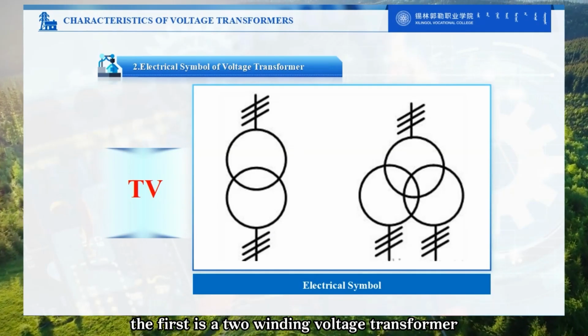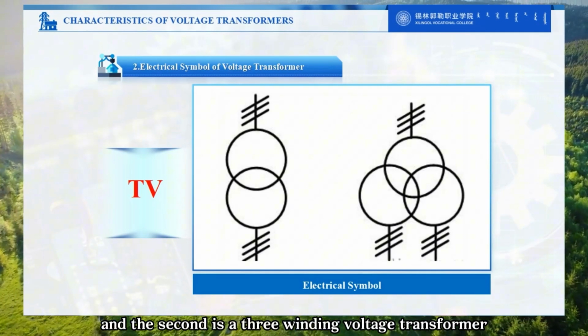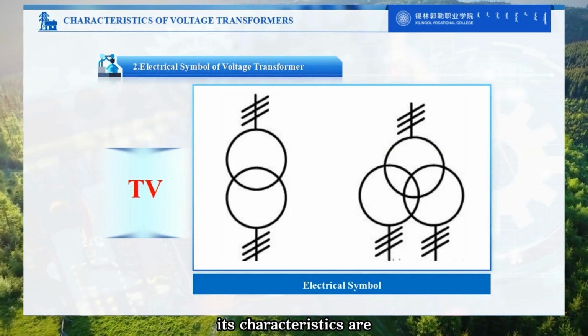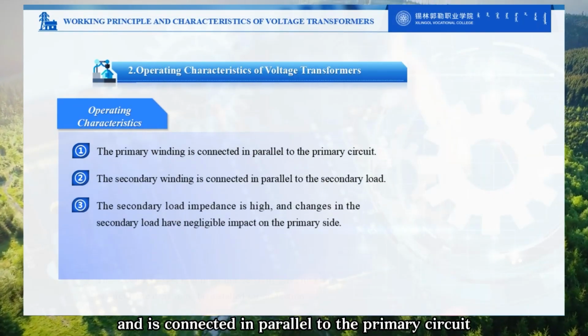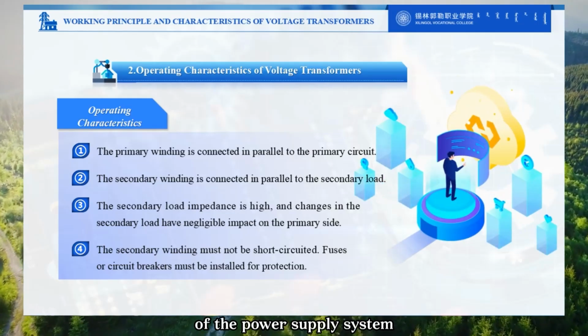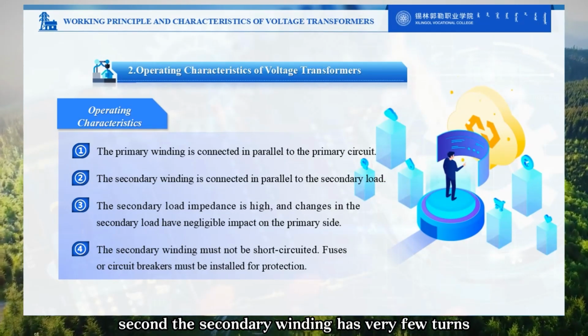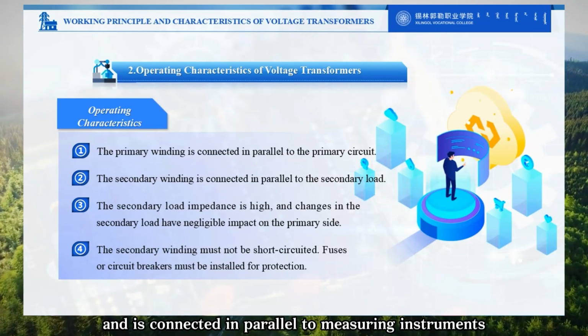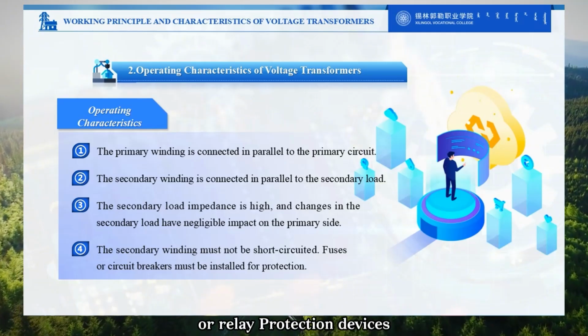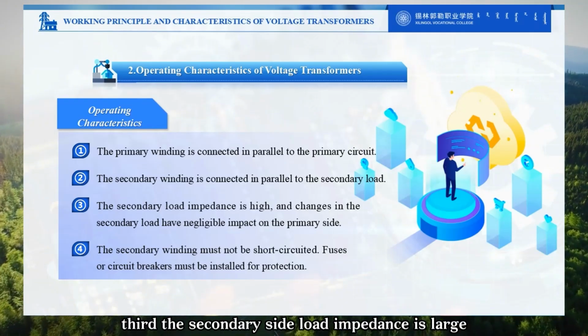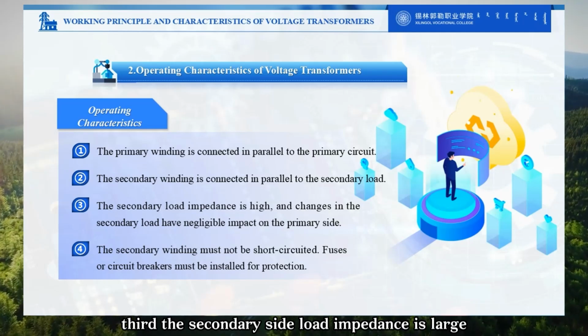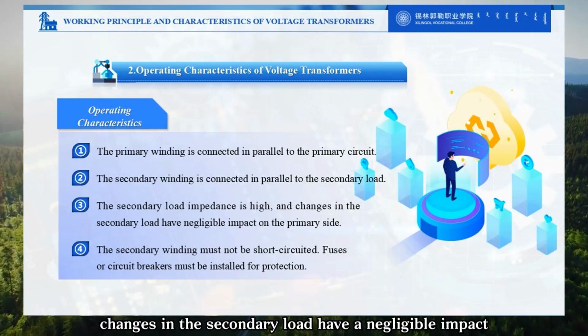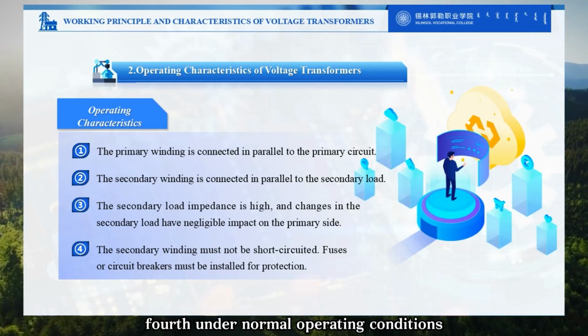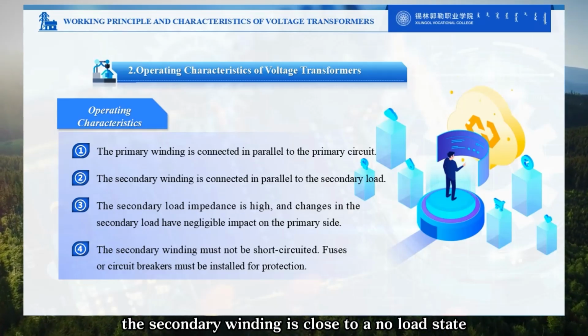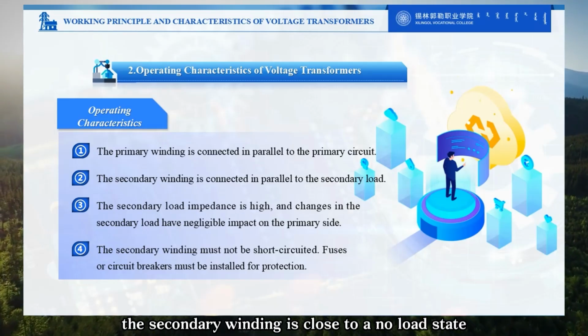The first is a two-winding voltage transformer, and the second is a three-winding voltage transformer. Its characteristics are: first, the primary winding has many turns and is connected in parallel to the primary circuit of the power supply system. Second, the secondary winding has very few turns and is connected in parallel to measuring instruments or relay protection devices. Third, the secondary side load impedance is large, so changes in the secondary load have a negligible impact on the primary side. Fourth, under normal operating conditions, the secondary winding is close to a no-load state.